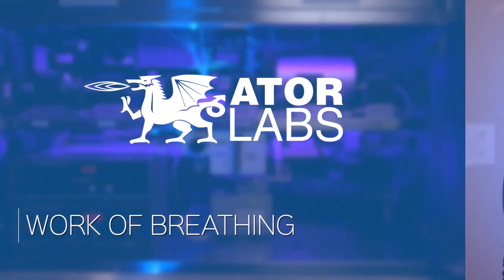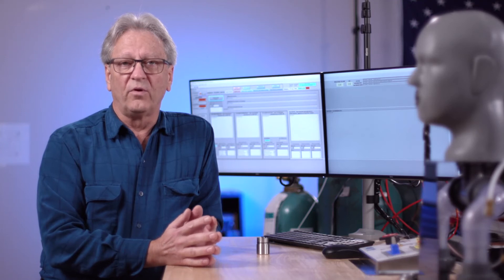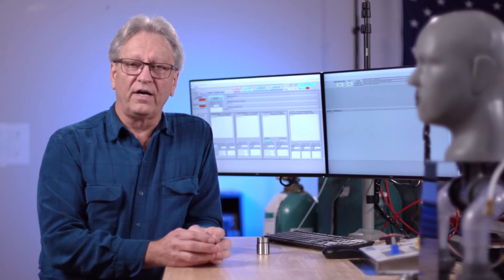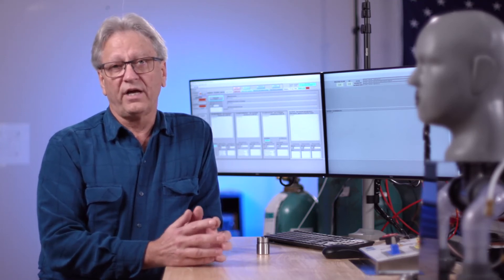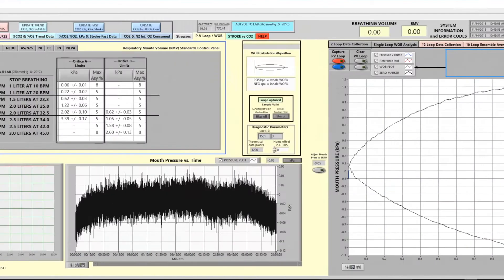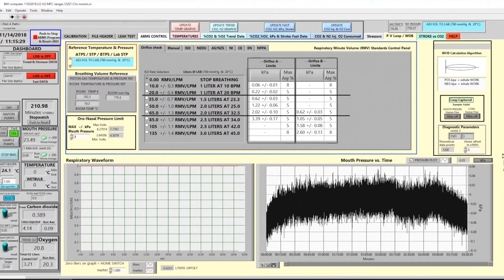In this video segment, we're going to explore a bit more of what the work of breathing capabilities are and how we verify that we match the ISO 16900 standard. Within our system, if we select the PV loop tab, we'll see the analysis screen on the right and the control on the left screen.